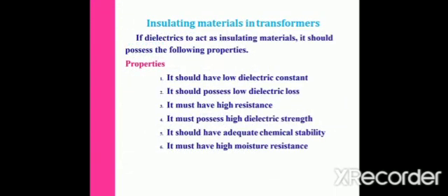For dielectrics acting as insulating materials in transformers, they should possess low dielectric constant, low dielectric loss, high resistance, high dielectric strength, adequate chemical stability, and high moisture resistance.